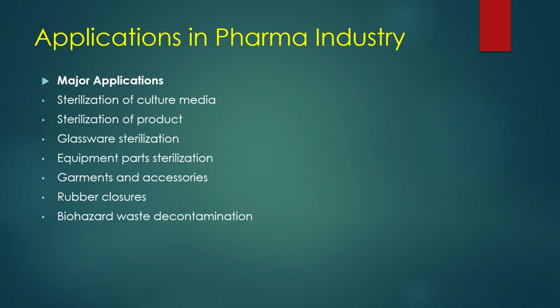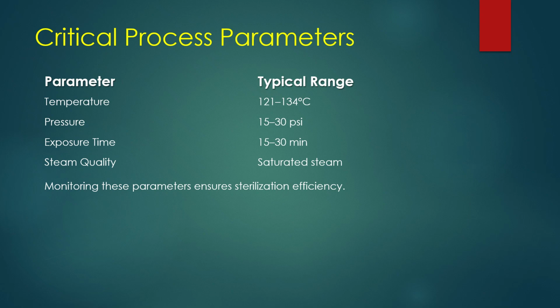Autoclaves are widely used in pharma industry for the sterilization of culture media, pharmaceutical products, glassware, equipment parts, garments and accessories. They are also used to sterilize rubber closures and for the decontamination of biohazardous waste, ensuring product quality, regulatory compliance, and patient safety. The effectiveness of an autoclave depends on maintaining critical process parameters, including temperature, pressure, exposure time, and the use of high quality saturated steam. The temperature should be between 121 to 134 degrees Celsius. The pressure should be between 15 to 30 psi and the exposure time should be between 15 to 30 minutes. Continuous monitoring and control of these parameters ensure effective sterilization, consistent process performance, and regulatory compliance.